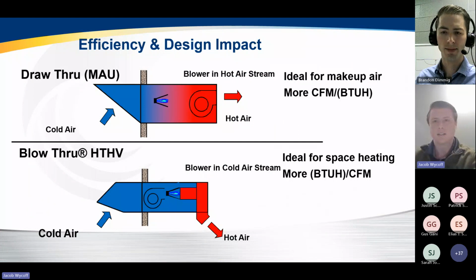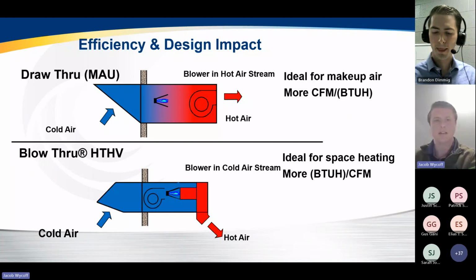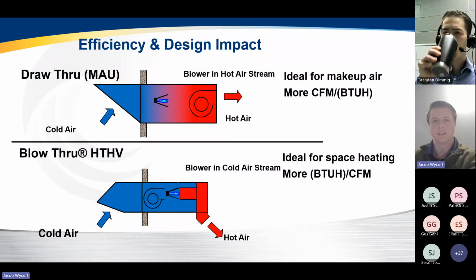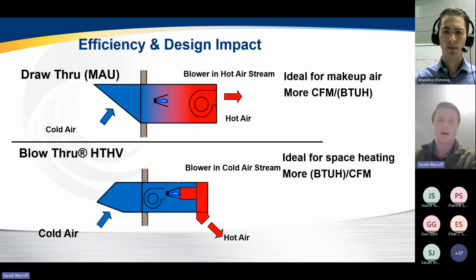Awesome. Yeah, so Brandon touched on this a little bit earlier, but I'm going to speak in a little bit more detail on how the design of the unit impacts the overall efficiency. As he mentioned earlier, with your typical draw-through unit, that burner is going to be upstream of the blower, which is going to restrict your discharge temperature to typically around 120 or less. That's really great if your primary goal is to provide large amounts of CFM as makeup air, things like kitchen makeup air units, paint booth makeup air units, applications where you have a lot of process exhaust and you're trying to make up that pressure differential.